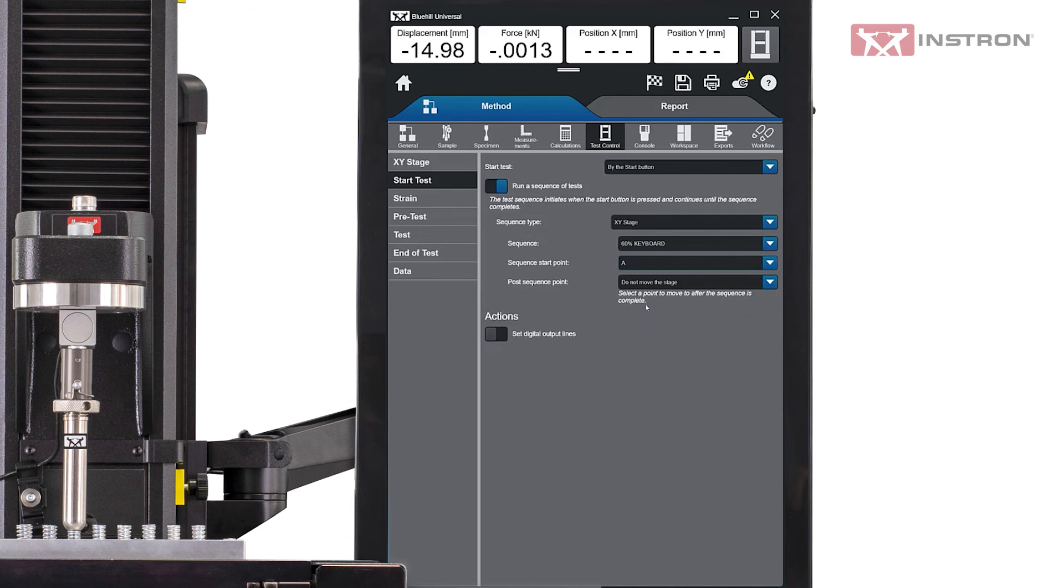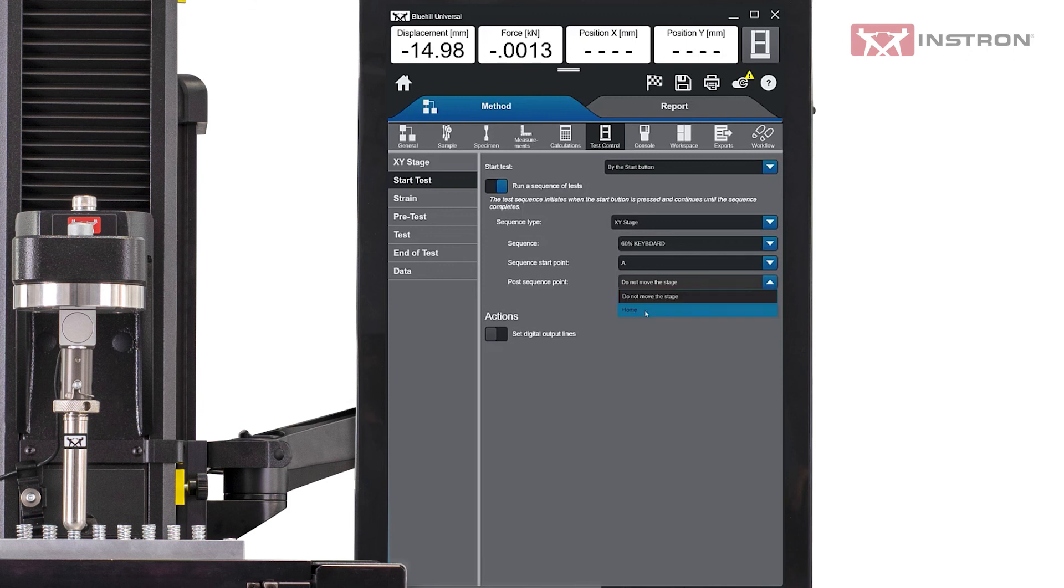Finally, the user can set an action to occur at the end of the test. The stage can remain at the last test location or it can be moved to the home position. Moving to the home position is helpful as it will leave the stage in a position where the user can easily remove the tested part and install a new sample.